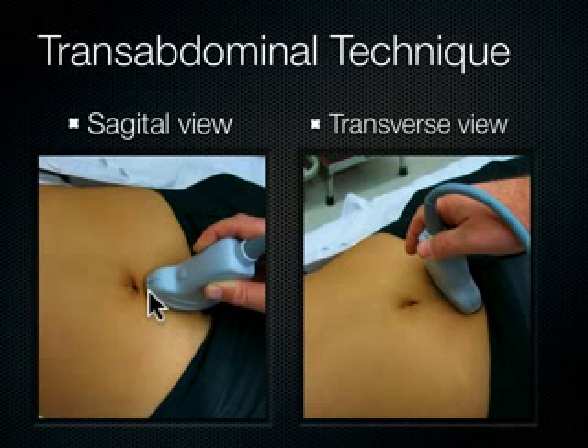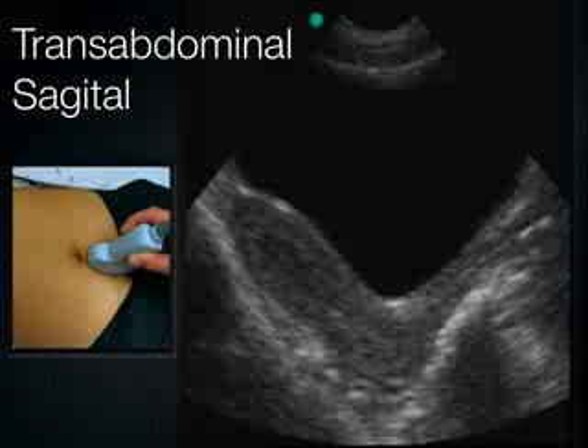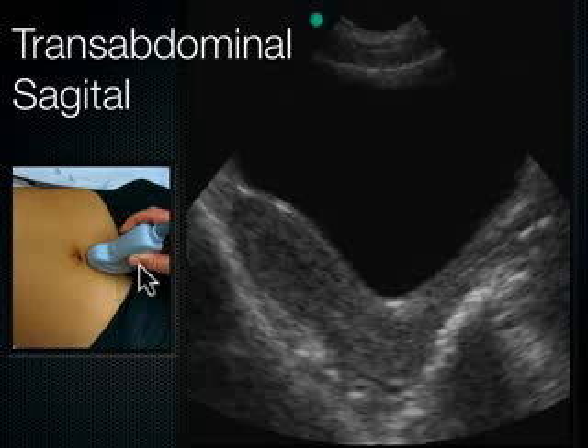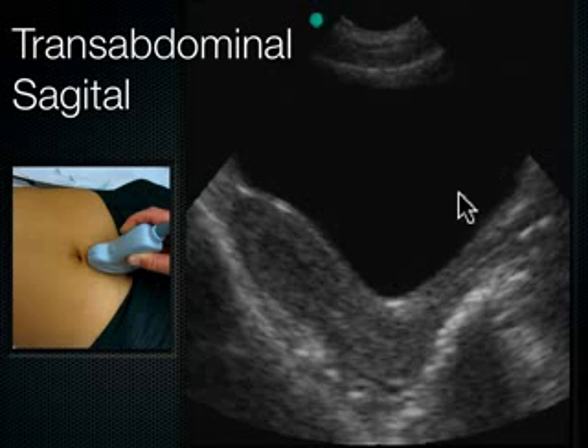When I have a C60, I will employ it in this fashion in the pelvis transabdominally, as opposed to using the other one, the smaller footprint P21. You can get away with that, but the C60 is really designed for this purpose. It's a better transducer to use if you have it available to you. Here's your C60 indicator towards the head. This is a very full bladder, as I mentioned. It's a triangular-shaped full bladder here.